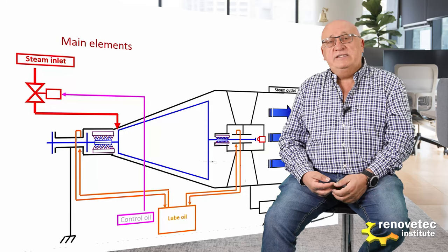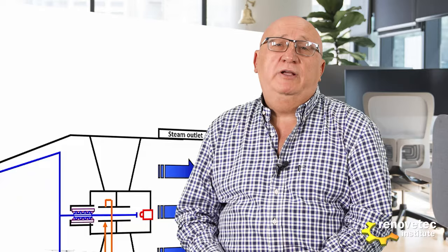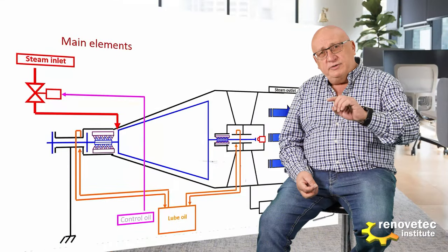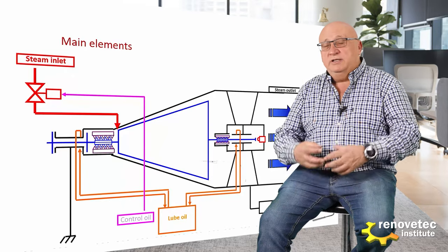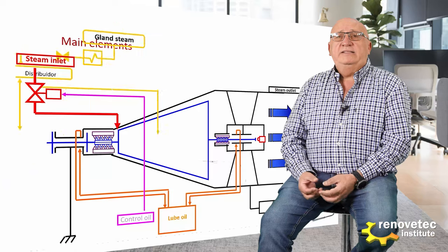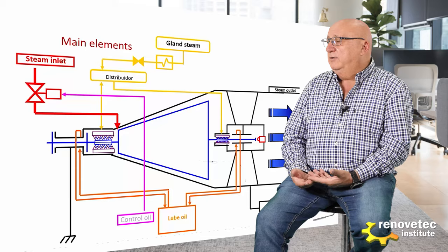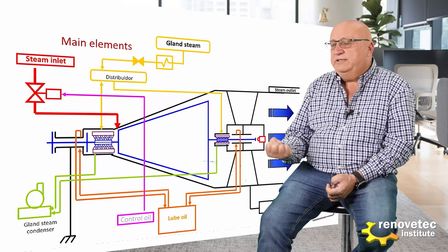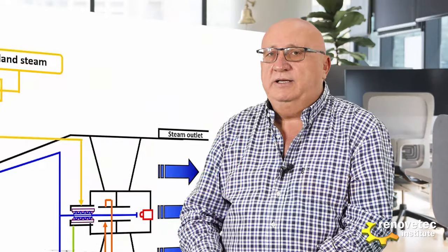The labyrinth seal blocks or inhibits the possibility of steam leakage on the two sides of the shaft. This mechanism provokes a loss of pressure and is very sophisticated. We will see in another video how the labyrinth seal works. The gland steam is one element needed to allow the labyrinth seal to work properly, and the gland steam condenser condenses the steam used to block the steam inside the turbine.